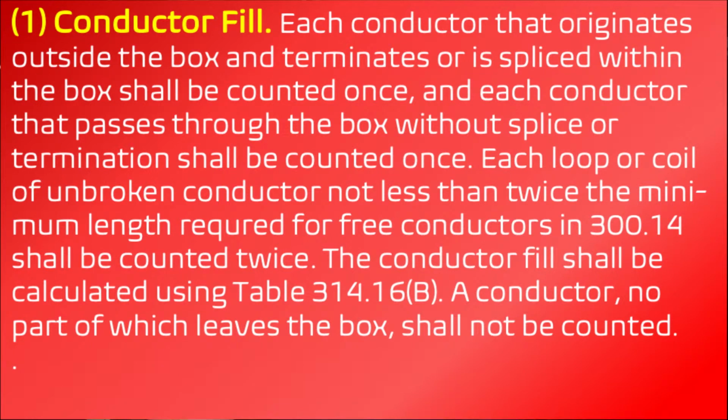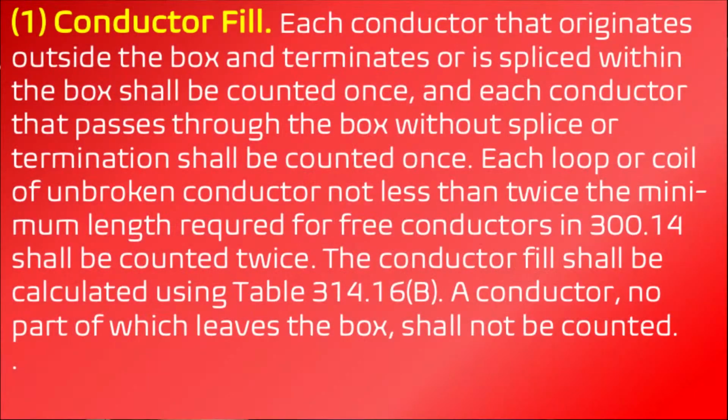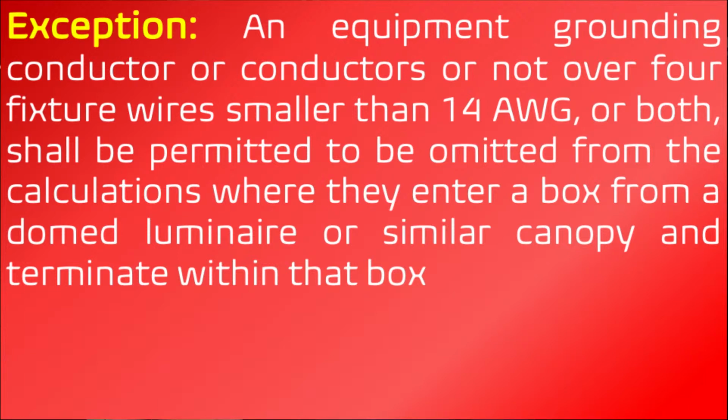The conductor fill shall be calculated using table 314.16b, and a conductor no part of which leaves the box shall not be counted. Now, here's the thing. I do have a slide for 314.16b, and that does give us the cubic inch fill of our conductor. So we'll get to that here right at the end before we start doing our calculations. So there's an exception with that rule.